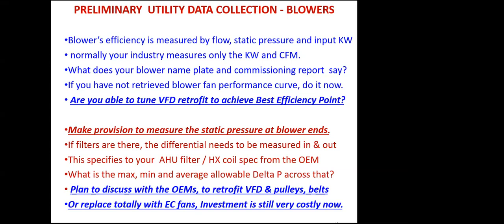By going by the cube law, if you are able to optimize the Pascal for the given blower, automatically you can achieve excellent savings. So you plan to discuss with the machine OEM, blower OEM, or the belt and pulley OEM to retrofit the VFD, pulleys and belts. Or you can replace the blower in your AHU with an EC fan, which is still at a nascent stage and very costly. People are afraid only of the initial cost, but the savings are excellent: with existing blowers you can achieve around 30% savings, and with an EC fan you can achieve even more. The more measurements you do on your given blower, the more it will show you the way to take your blower next. Next, please.